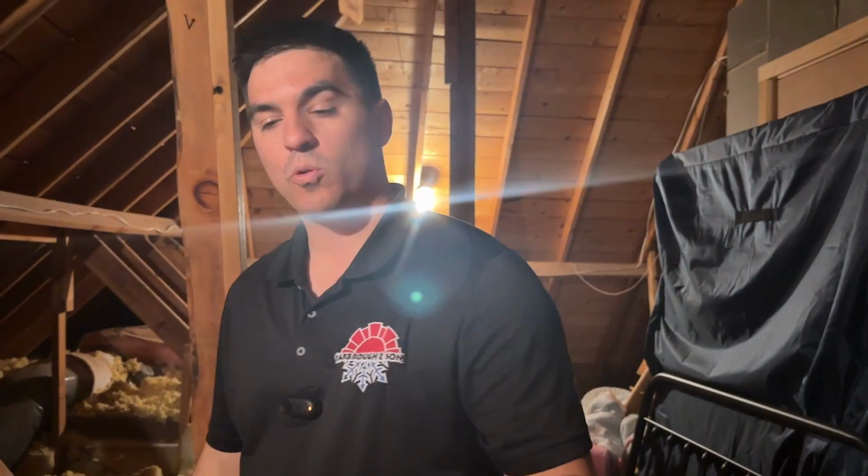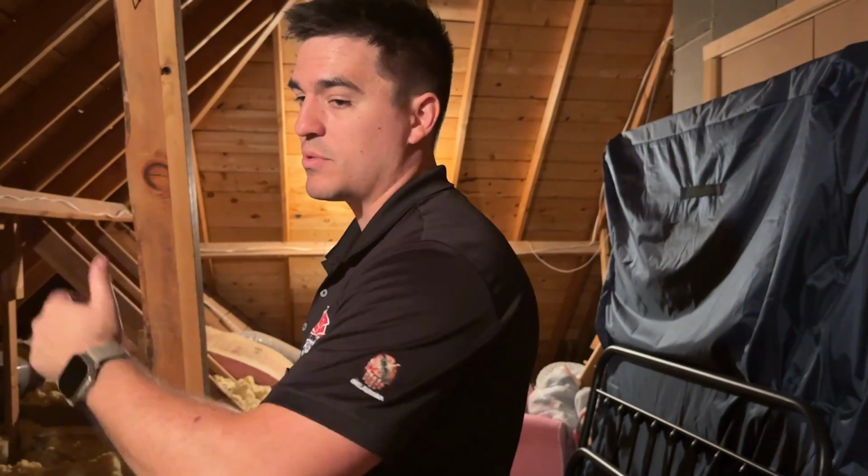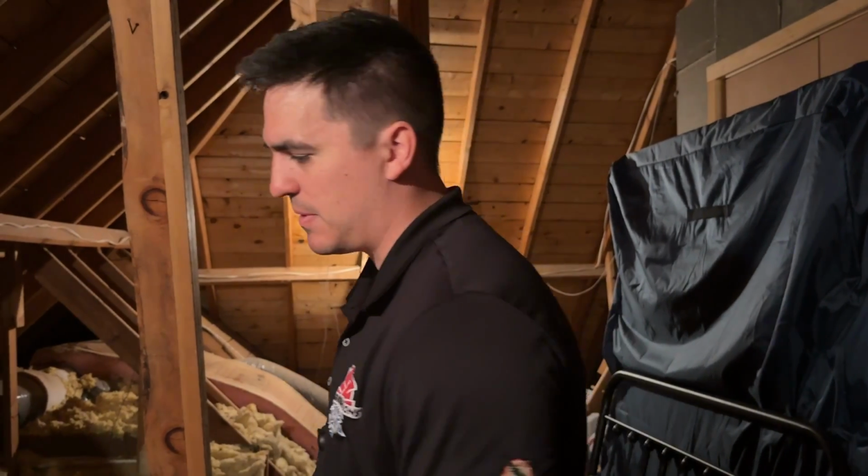Now, the homeowners are new to the home. They've only lived in this house for 2 years. And so their temperature preference is probably higher than that of the people before them. Ten years ago, this may have been sized perfectly for their preferences. I would say that's probably the biggest hurdle we're having to solve for: why did this system start having major problems around 10 years old? And it can happen.